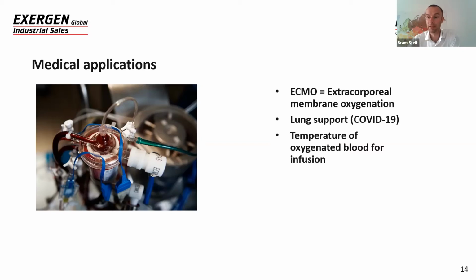But the blood that's going back into the body needs to be 37 degrees. So there's a heat exchanger in there to make sure that the blood is warmed to 37 degrees. You don't want to go too high, because that can destroy the cells. You don't want to go too low, because that could cool the body temperature of the patient. Both are things you want to avoid. So this is one where our IRTC sensors measure blood temperature through medical tubing.